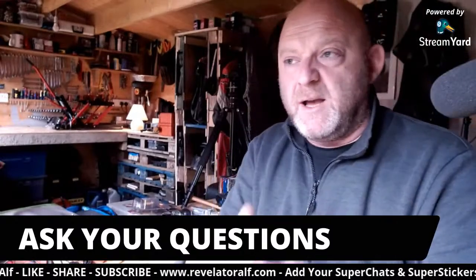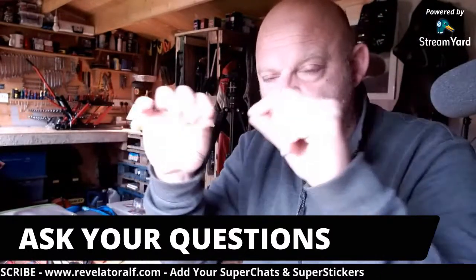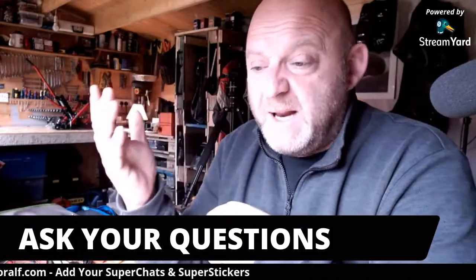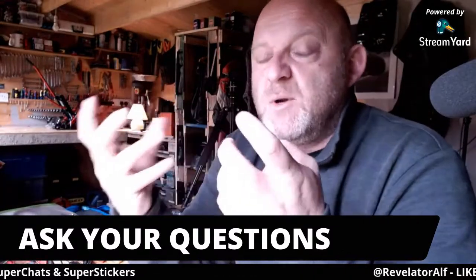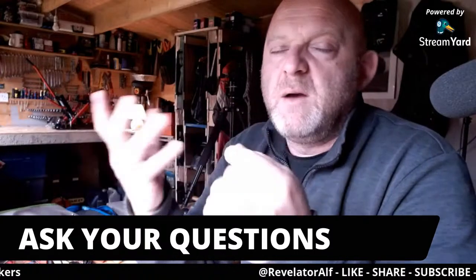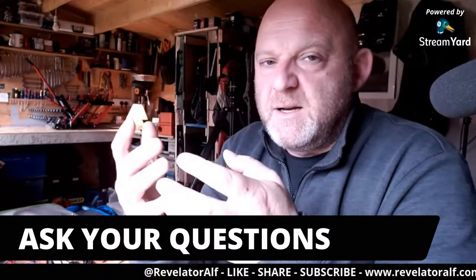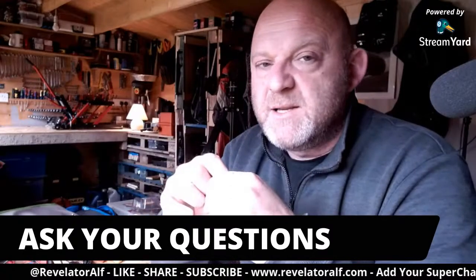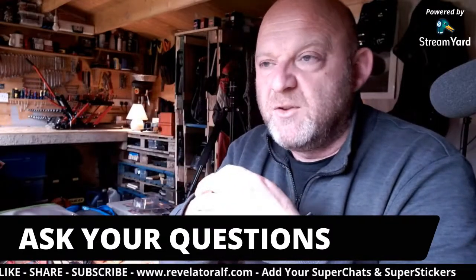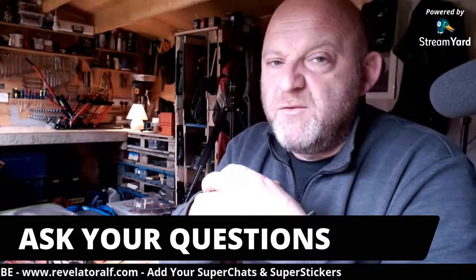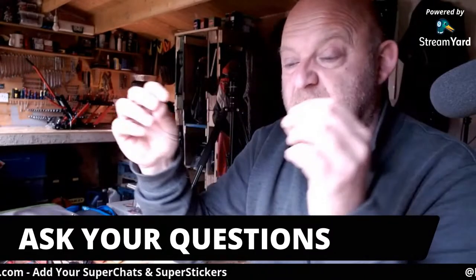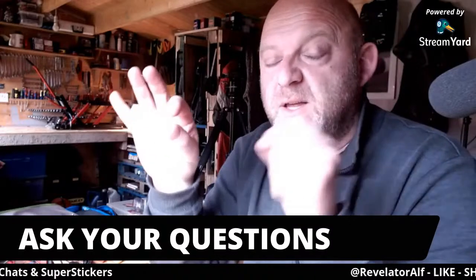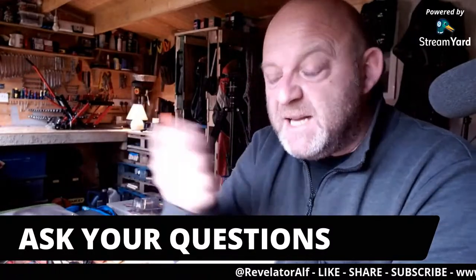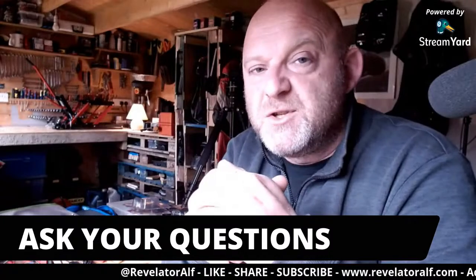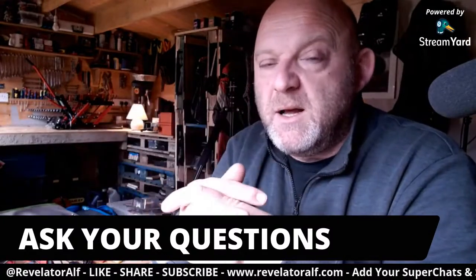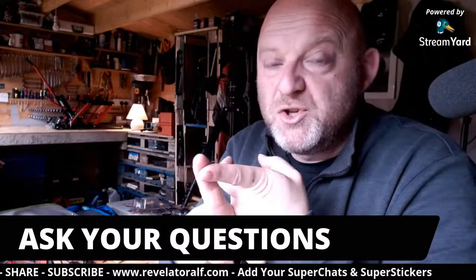You decide, right, okay, I'm going to just put a good solid connection, put the wiring through, and it works. But if it isn't sealed up properly, you've got to think, well, maybe moisture can get in there. So then we talk about soldering wiring together, wrapping it in insulation tape afterwards. And then you think, well, maybe that's not working very well. So another technique is to put an insulation piece over the wire you just joined and heat it up so it shrinks, which helps with the integrity and also prevents moisture getting in.